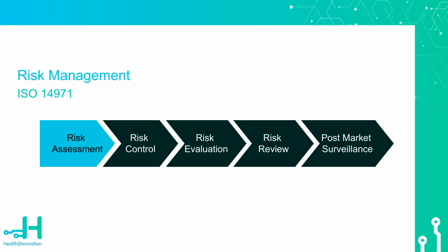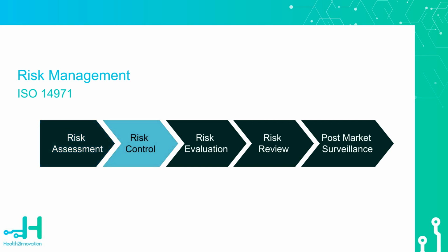We want to identify what could go wrong, or how could someone get hurt by using our device or using our device incorrectly. We should consider if there is a sequence of events or situations where faults might occur. We then want to identify what risk control measures could be available to us to address these situations. This could be design concepts or instructions to user to clarify ways to safely operate the device. It could also be done by restricting access to the device through contraindications in our labeling. We will need to be able to verify and validate the risk control to prove its effectiveness.